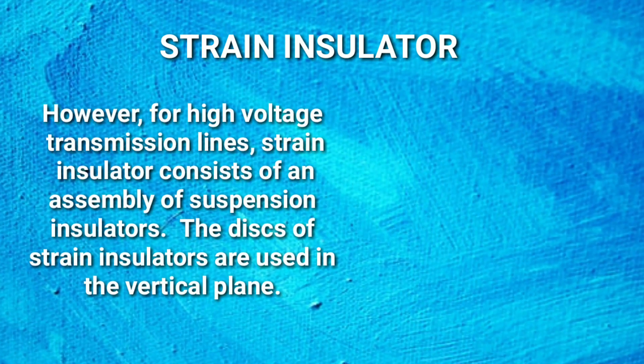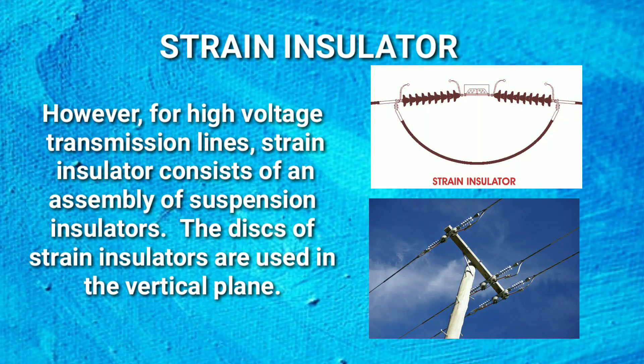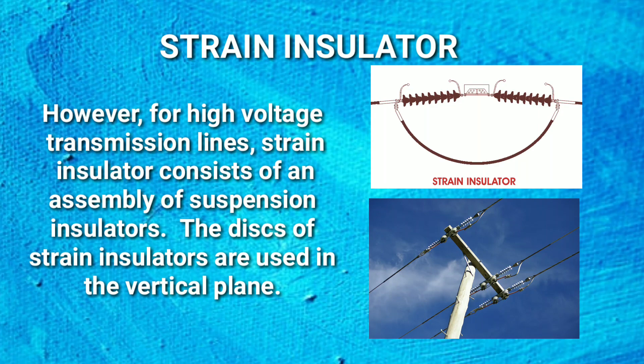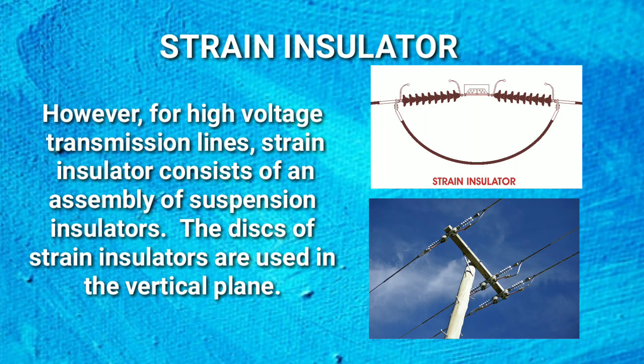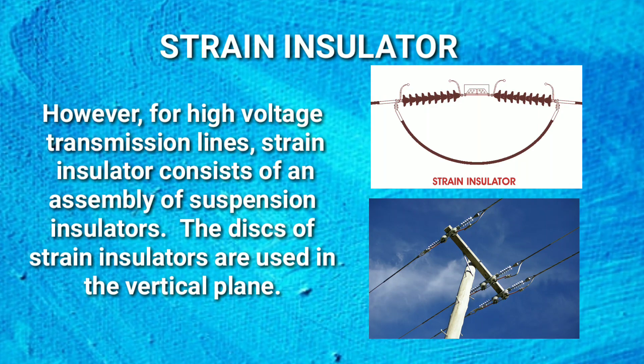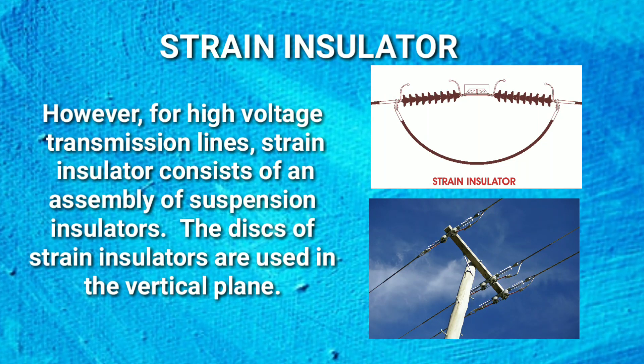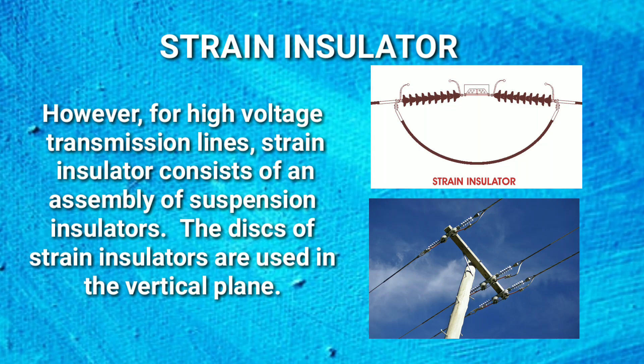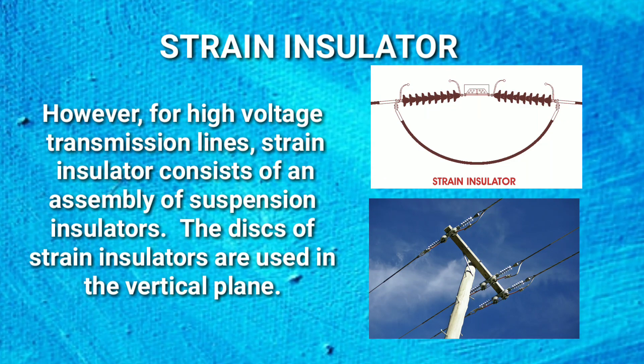However, for high voltage transmission lines, strain insulator consists of an assembly of suspension insulators. The discs of strain insulators are used in the vertical plane. When the tension in lines is exceedingly high, at long river spans, two or more strings are used in parallel.